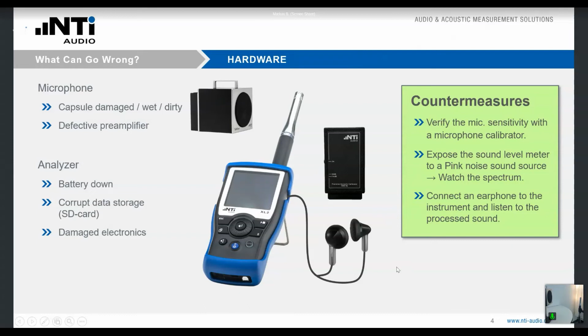Second area, the instrument setup. Again, we have to take a close look at the microphone and especially at the sensitivity of the microphone. You certainly know that each microphone is an individual device with an individual sensitivity. The sensitivity stands for the ratio by which the microphone converts the sound pressure waves into an electrical signal. So if this sensitivity is set wrongly in the instrument, the analyzer will misinterpret the electrical signal and this will lead to completely wrong measurement results. So it's very important that the sensitivity is adjusted correctly.